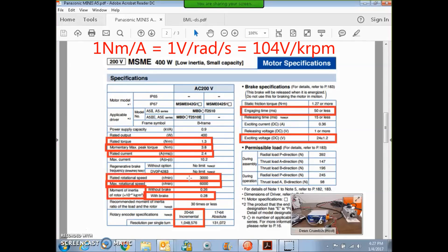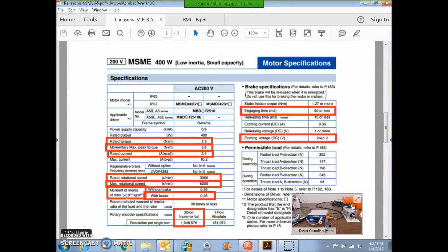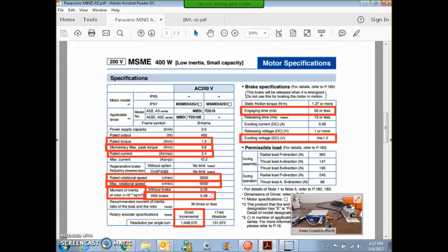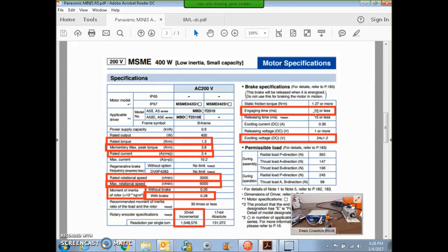The normal rotation speed is 3,000, the max theoretical is 6,000, and I've got the inertia, 10E minus 4 kilogram meters squared, so 0.28 kilogram centimeters squared. 20-bit incremental, 1 million counts. The incremental comes with halls, 24-volt brake. Engagement time is 50 milliseconds for the brake.